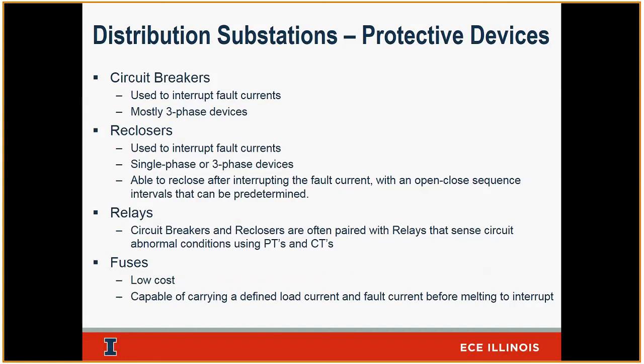Fuses, the poor man's way to protect the distribution system. Right? These are old technology, existed for a long time, but it still is reliable and it's used across the system. We use it typically on taps. We don't use it on the primary. So we'll talk about what a primary system is, but primary is, you know, when you come out and you're three phase, so you have three lines, A, B, and C, and they all go out of the substation, go out into the world. Your houses or your apartment buildings could be fed by just one single phase. That's when we call it the tap. So you tap off here, this could be a house, feeding just one customer, maybe multiple customers if they're living off a building. On taps, we try to protect those with a fuse.